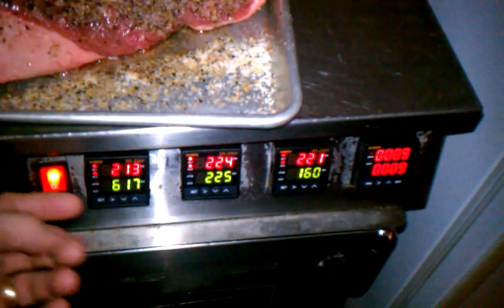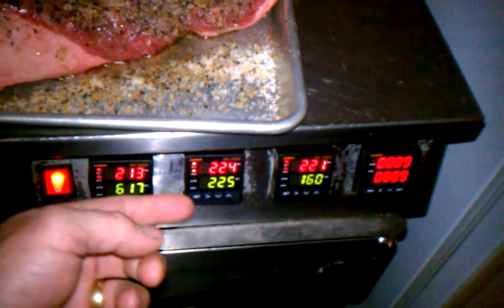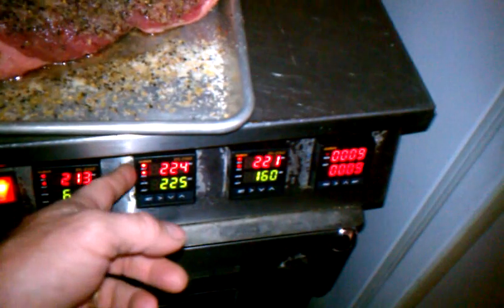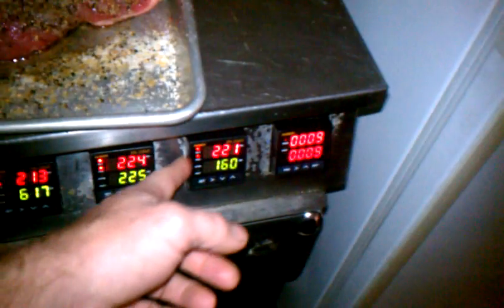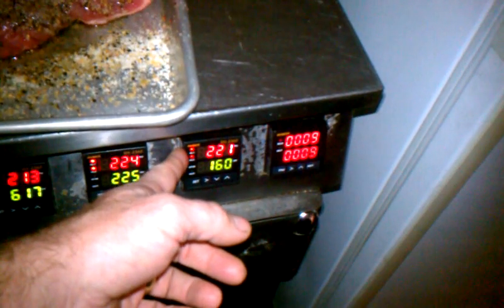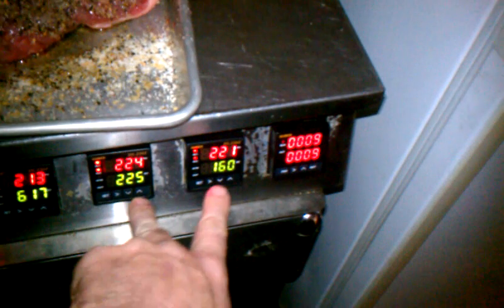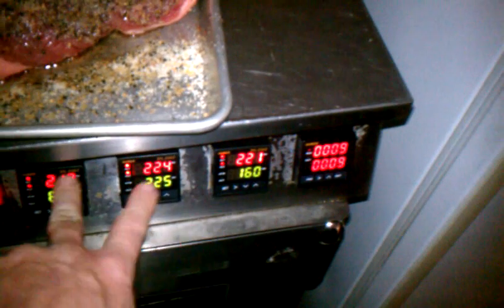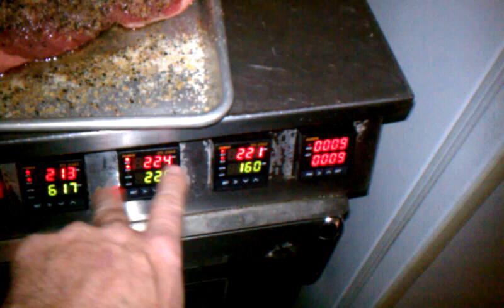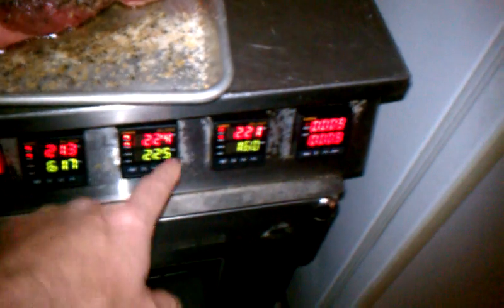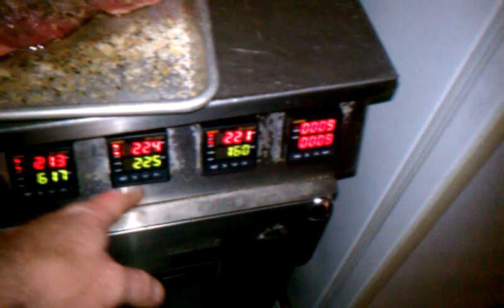Once it does that, it sends an alarm output to J2, which shuts this one off and allows this one to take over. Both of these are wired to the same solid-state relay, with just two sets of wires running back to that relay. So since this one is at a higher temp, it takes precedence over this one.